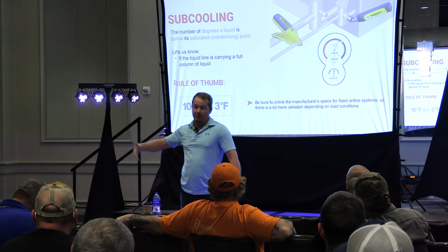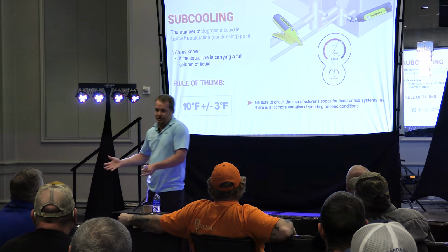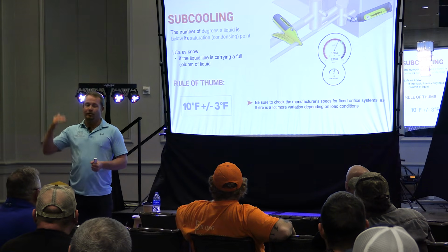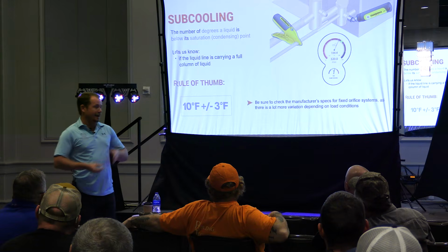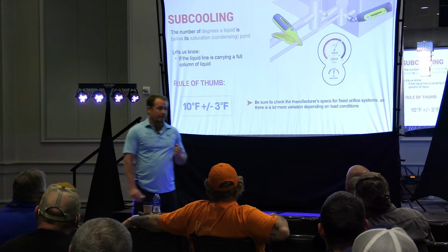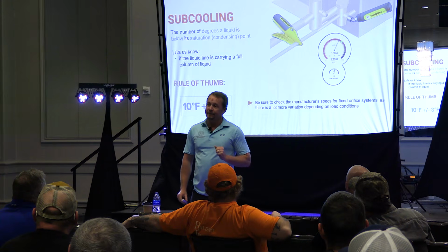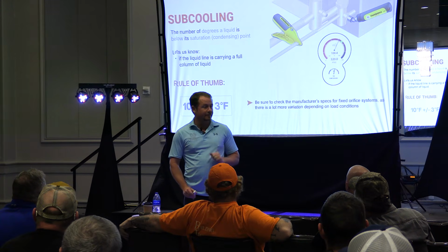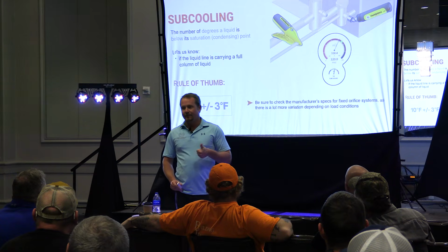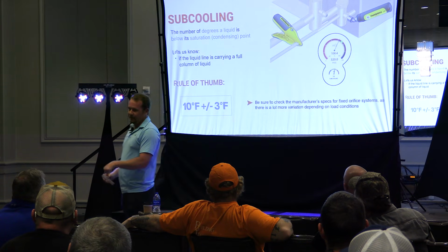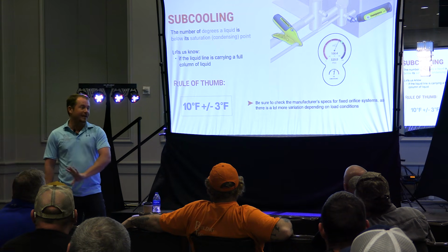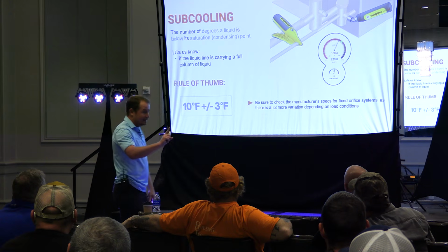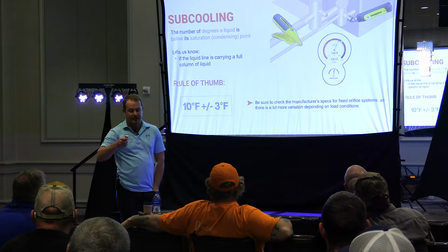Now, the manufacturer gives us that number for a reason. And so it's good that you adjust the charge to hit manufacturer specs. But if the goal was to try to get her more capacity out of the equipment, that did not solve the problem. In the same way that when the new guy goes out nowadays and he says, I fixed the problem. It only had 7 degrees of subcool, and I adjusted to what the manufacturer said, which was 11. Now we're good, right? No. You actually made the system perform worse by doing that. Now, if that's what the manufacturer said that you need, then good on you. I'm glad you did it. But you didn't improve the capacity of that piece of equipment unless it was resulting in flash gas at the metering device. Make sense?